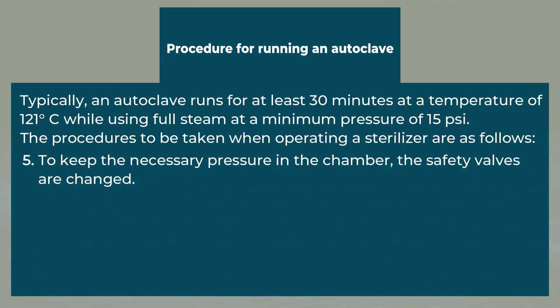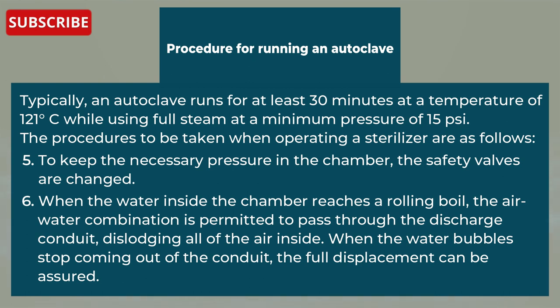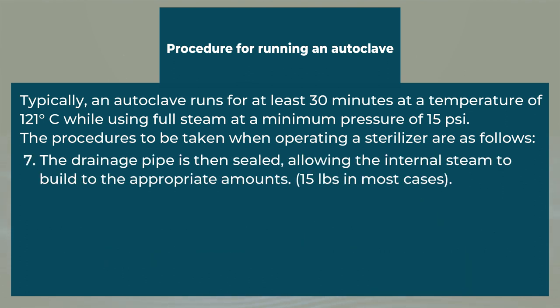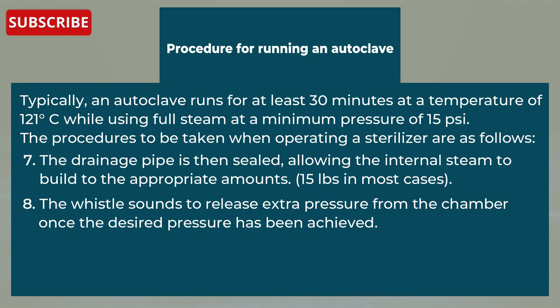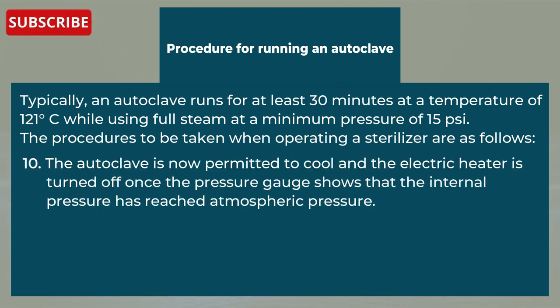Fifth, change the safety valves to keep the necessary pressure in the chamber. Sixth, when the water inside the chamber reaches a rolling boil, the air-water combination is permitted to pass through the discharge conduit, dislodging all of the air inside — when the water bubbles stop coming out of the conduit, full displacement can be assured. Seventh, the drainage pipe is then sealed, allowing the internal steam to build to the appropriate amounts. Eighth, the whistle sounds to release extra pressure once the desired pressure has been achieved. Ninth, the autoclave runs for a holding time after the whistle, typically 15 minutes. Tenth, the autoclave is permitted to cool and the electric heater is turned off once the pressure gauge shows the internal pressure has reached atmospheric pressure.